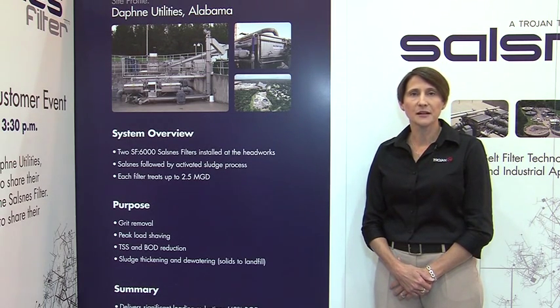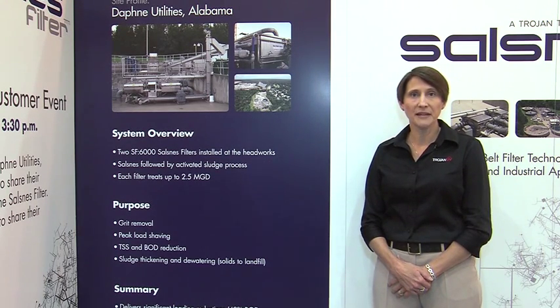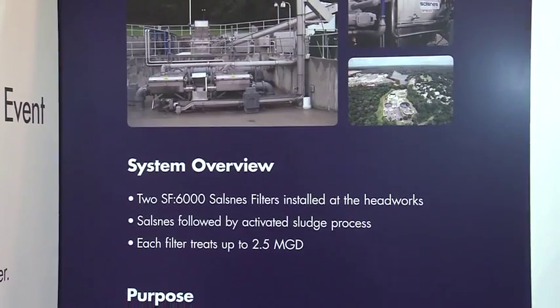One project we're featuring is Daphne Utilities in Alabama, just next to the Mobile River. Their challenge was to manage peak flows that were bringing high influent TSS and BOD to the plant and stressing downstream processes. With two SF6000 Salsnes filter units, they were able to shave peak loads by removing 65% of the TSS and 40% of the BOD.